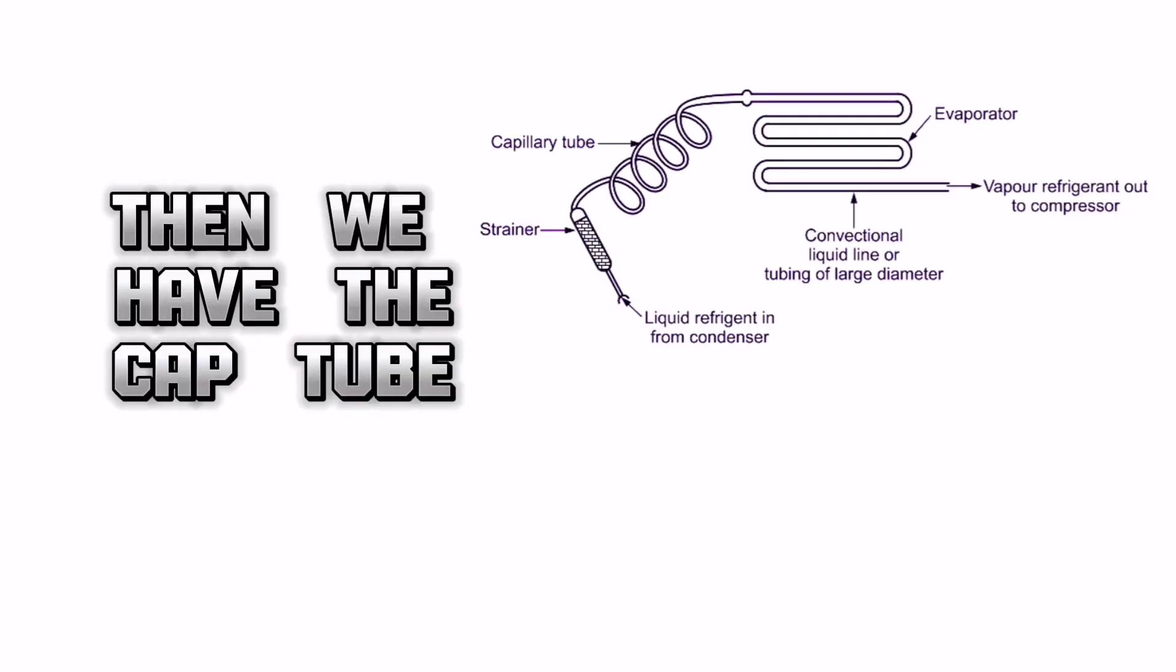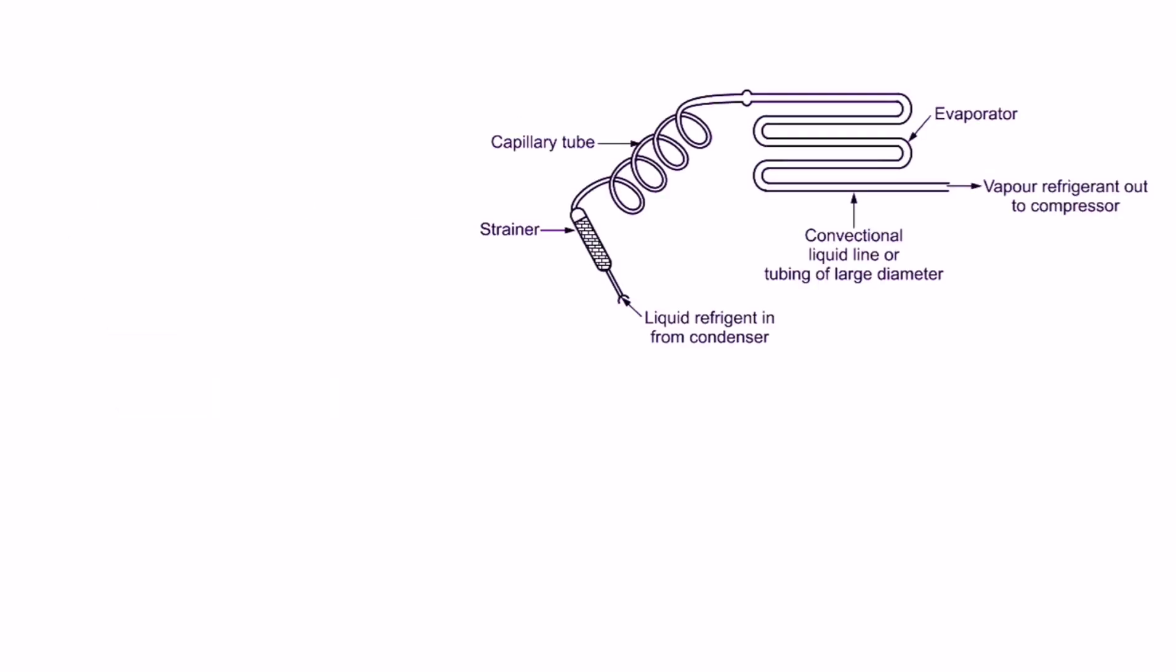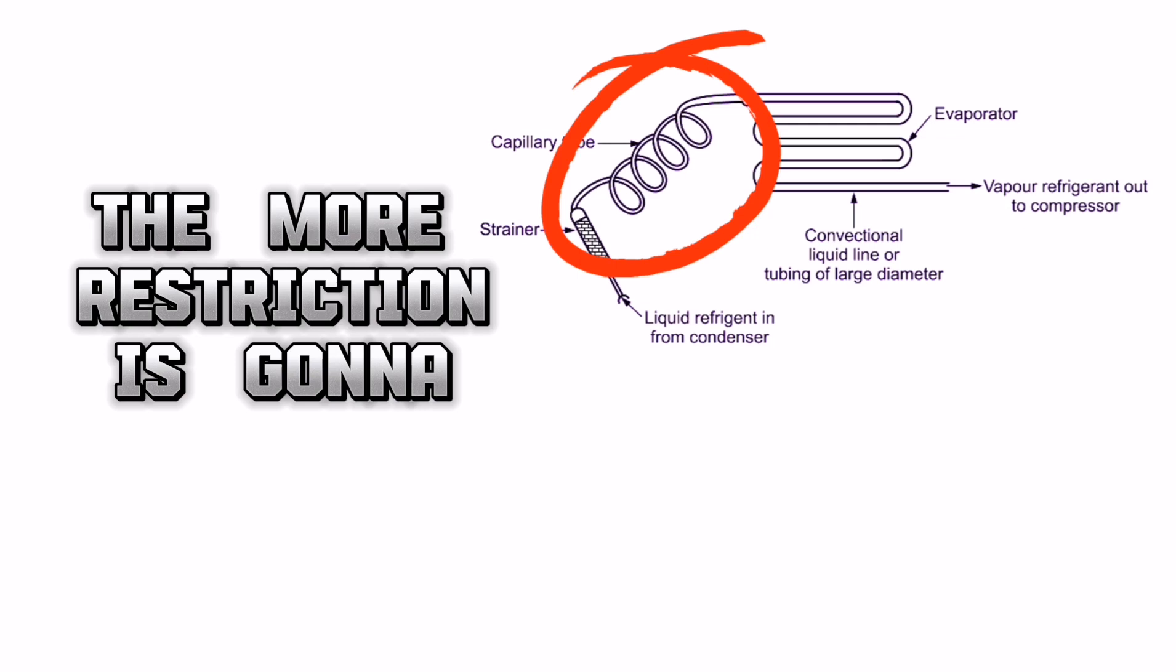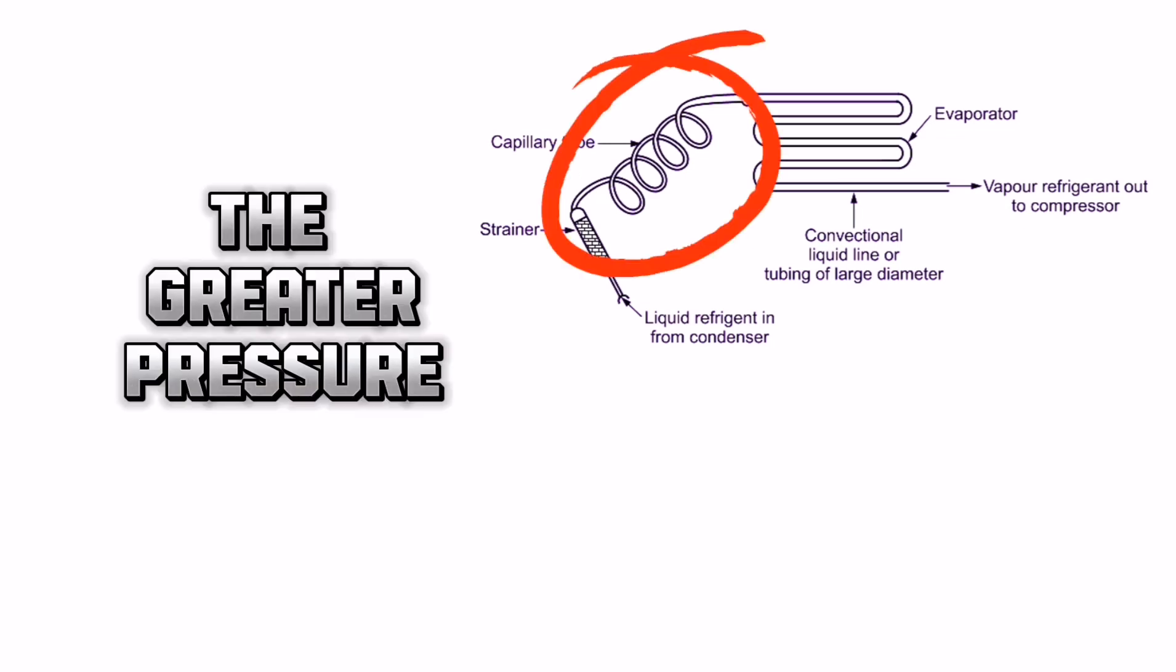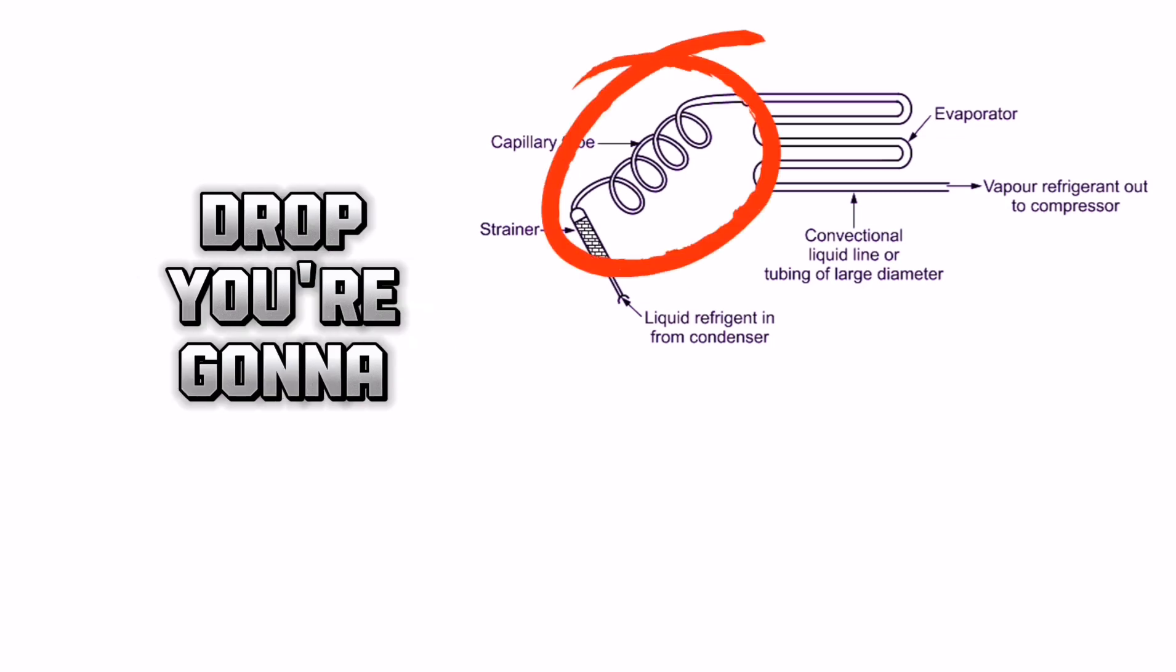Then we have the cap tube, capillary tube. All this is, is just a long piece of tubing. The longer it is, the more restriction it's going to have. The smaller the inside diameter is, the greater pressure drop you're going to have.